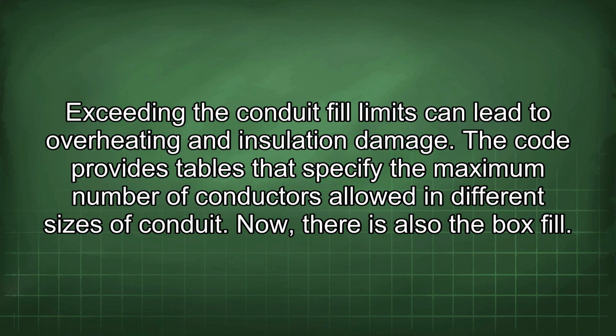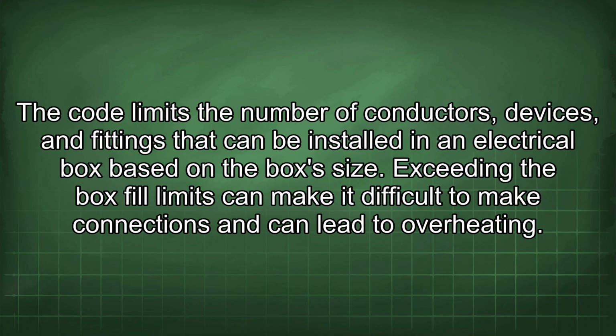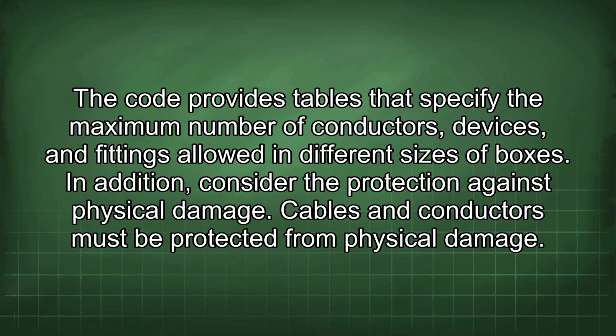Now, there is also the box fill. The code limits the number of conductors, devices, and fittings that can be installed in an electrical box based on the box's size. Exceeding the box fill limits can make it difficult to make connections and can lead to overheating. The code provides tables that specify the maximum number of conductors, devices, and fittings allowed in different sizes of boxes.